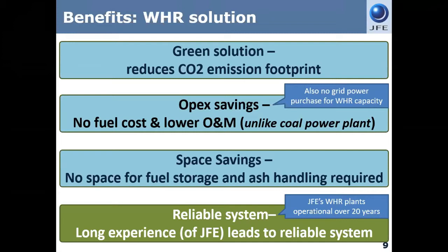Why is this waste heat recovery important for JFE? We believe this is green. It can reduce the CO2 emission footprint, especially because Japan and Indonesia also signed the Paris Agreement and Kyoto Protocol, so every bit reduces the CO2 footprint. The second important point is OPEX saving, because you don't need fuel - you just recover the heat that would otherwise be thrown into the air, and then use it. There's also space saving, since there's no space needed for fuel storage system.